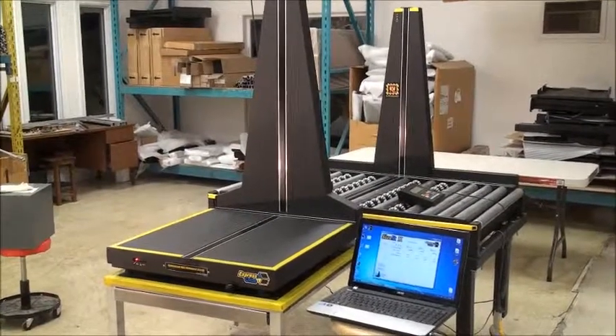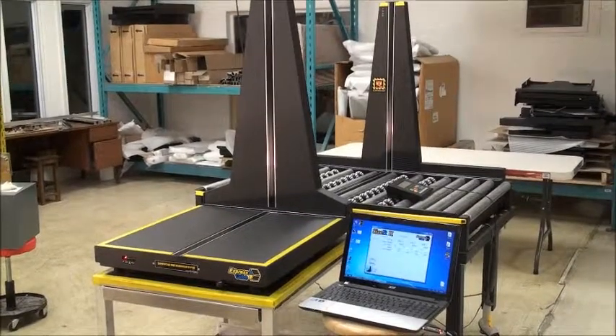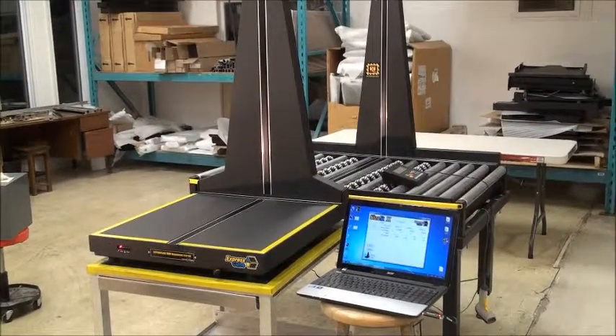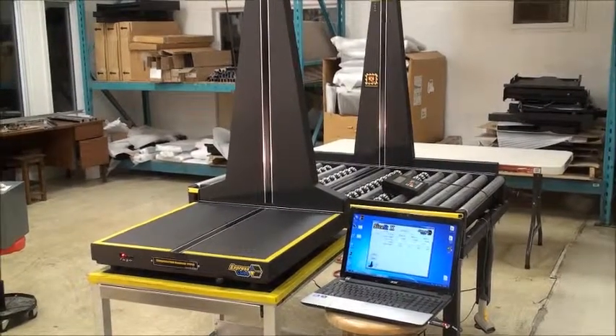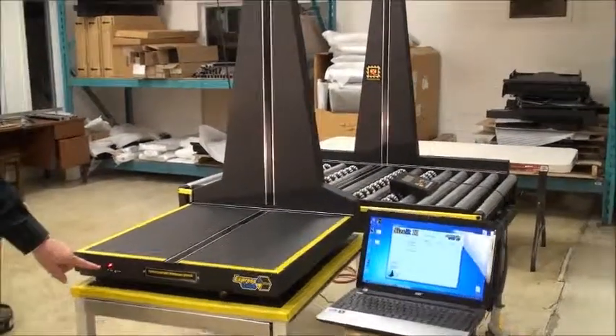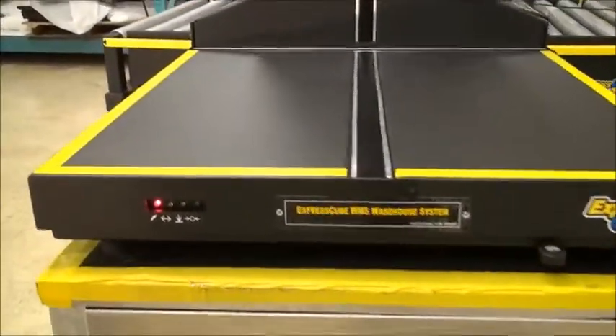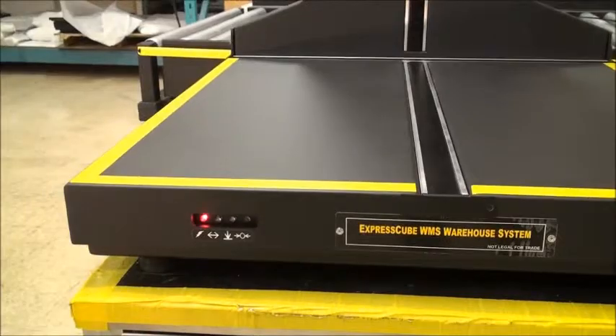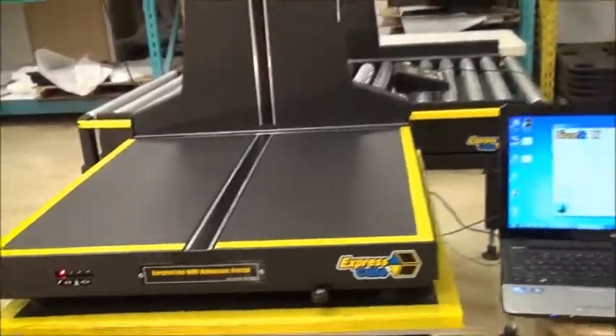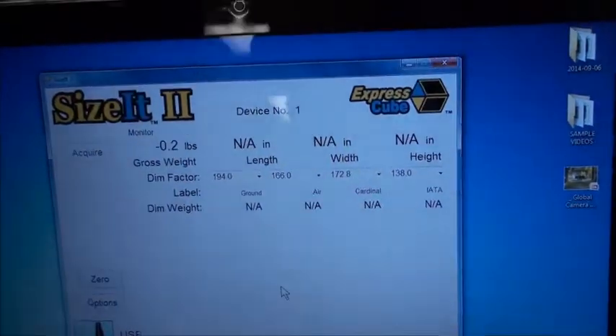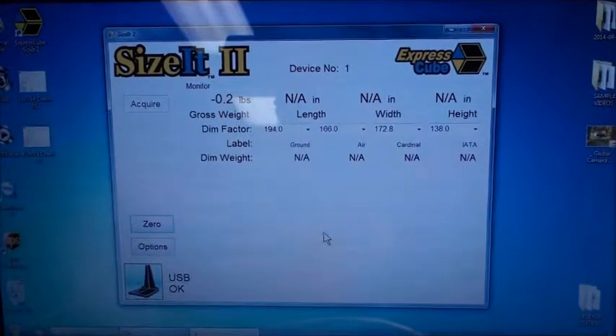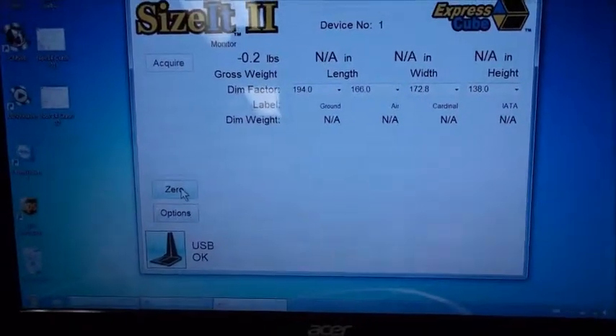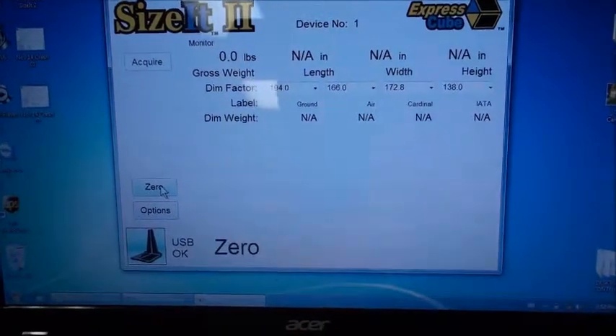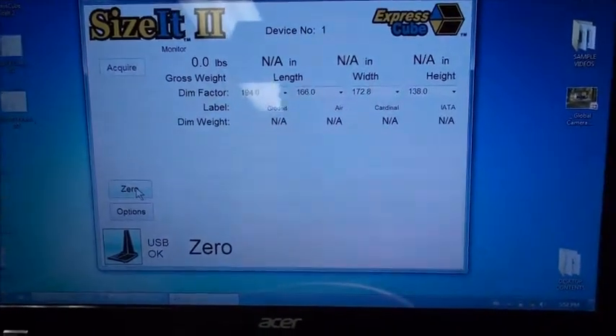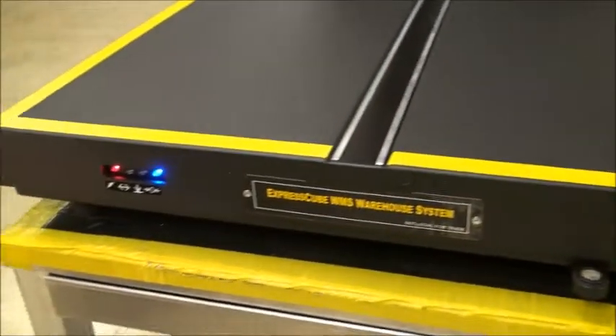Okay, on the 265, we're going to show you how to set up before you start using it with the computer as the controller. In this case here, if you take a close look at the status lamps, you'll notice only a red on. And the fact that you don't see a blue with an empty table is your first hint that actually it needs zeroing. And sure enough, if you look at the SizeIt, you'll see a weight on there that doesn't actually exist. So the first thing we can do is zero the table out. Now you'll see 0 shows up here, and you'll also now see blue on the display.